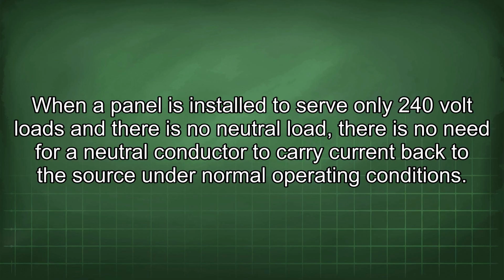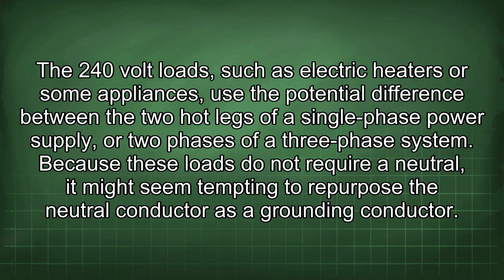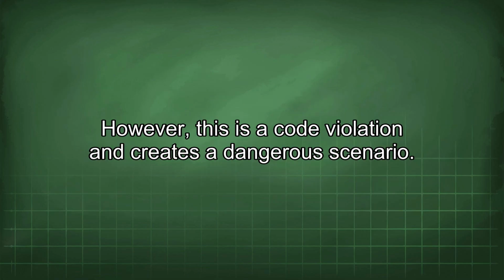When a panel is installed to serve only 240-volt loads and there is no neutral load, there is no need for a neutral conductor to carry current back to the source under normal operating conditions. The 240-volt loads, such as electric heaters or some appliances, use the potential difference between the two hot legs of a single-phase power supply, or two phases of a three-phase system. Because these loads do not require a neutral, it might seem tempting to repurpose the neutral conductor as a grounding conductor. However, this is a code violation and creates a dangerous scenario.